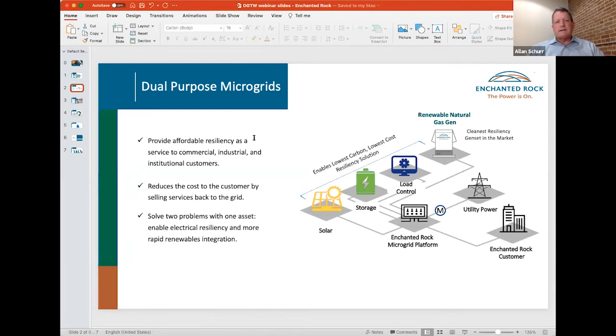The customer receives the level of resiliency they're looking for. 5 nines is commonly talked about, but what it really means for most customers is they don't want outages, and when an outage occurs, they want minimal disruption and to be back in operation as quickly as possible. With a grid synchronous interconnection, this microgrid can react quickly when there's an outage, or can even proactively island to protect from a power outage. On return to utility service, there would be no blink at all. That really provides the cleanest way of getting power on a continuous basis and during emergency operations.